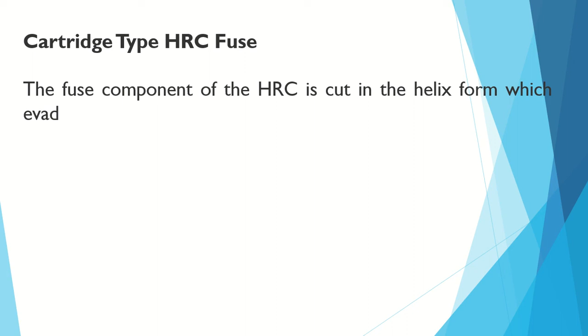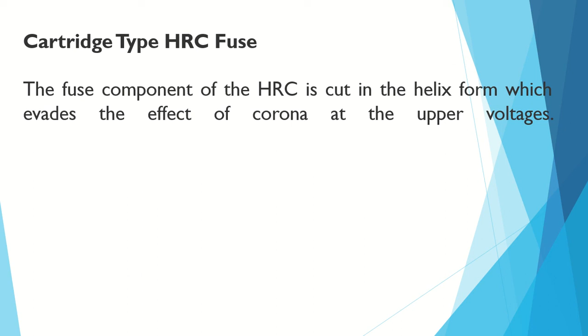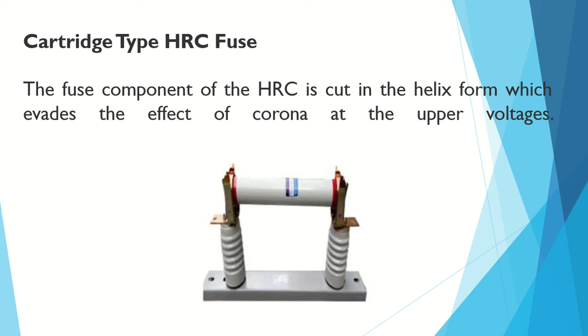Next is the cartridge type HRC fuse. The fuse component of the HRC is cut in helix form, which avoids the effect of corona at higher voltages. This cartridge type HRC fuse can be found in substations.